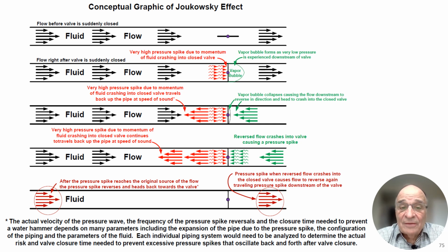But when you're designing valve closures, you have to design them not to instantaneously close. So they need to close in a manner that is slow enough to avoid this effect. Typically, plants are designed to operate where valve closures, especially on large piping, take 1 to 2 seconds per diameter inch. So a 30-inch pipe might have a valve closure that takes 30 seconds to close that valve, so that the closing of that valve does not cause that pressure hammer.